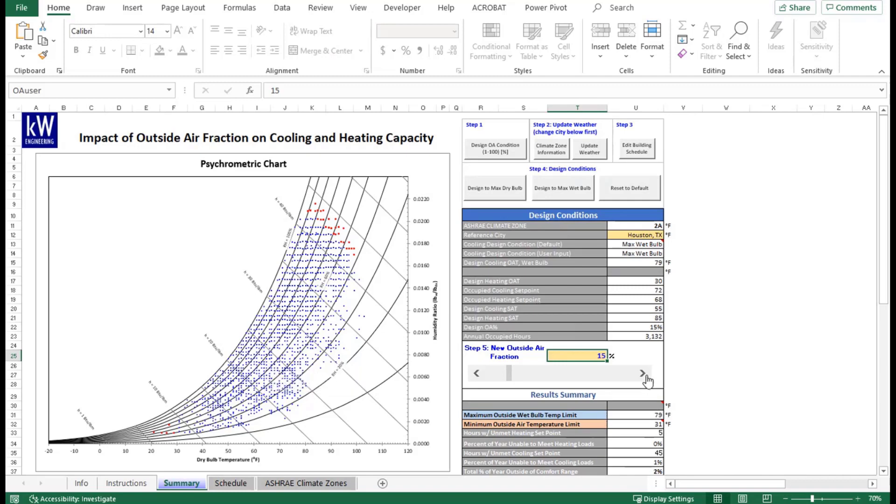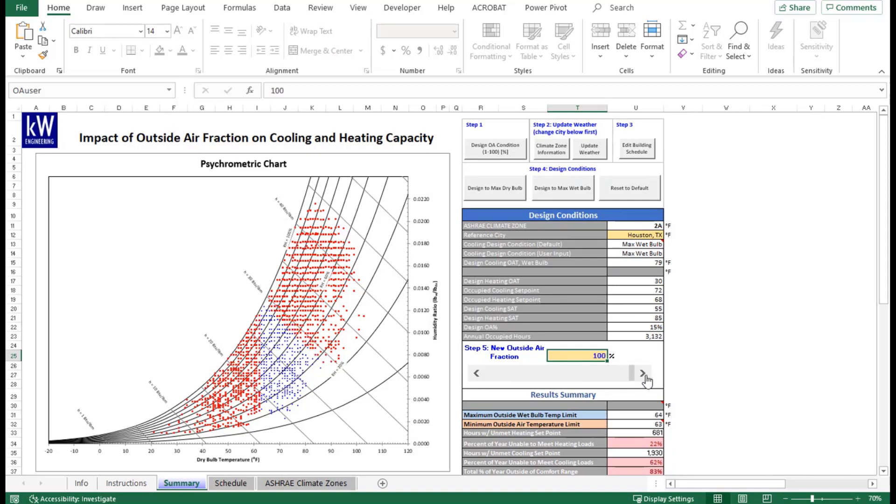Now we go ahead and increase it further. You'll be able to see the real impacts of adjusting that outdoor air fraction on your building. The short of it is, essentially, most buildings have that design condition of 15% to 30%. When you do start to increase that outdoor air fraction, during the more extreme periods of the year, whether that's summer or winter, or depending on your climate region, that could vary, you'll run into issues where your HVAC equipment won't be able to handle the load. This tool just allows the user to see all of those impacts.